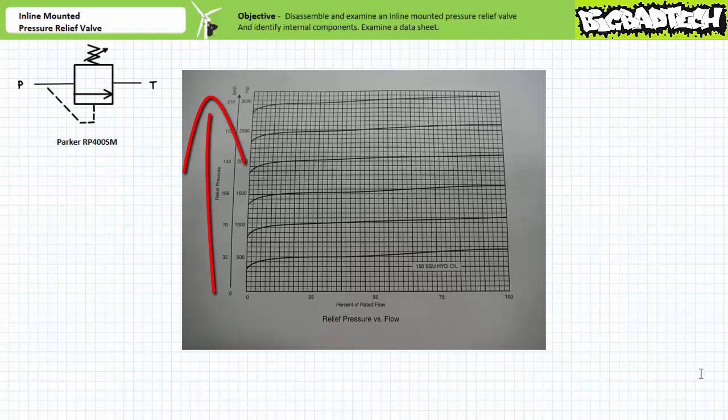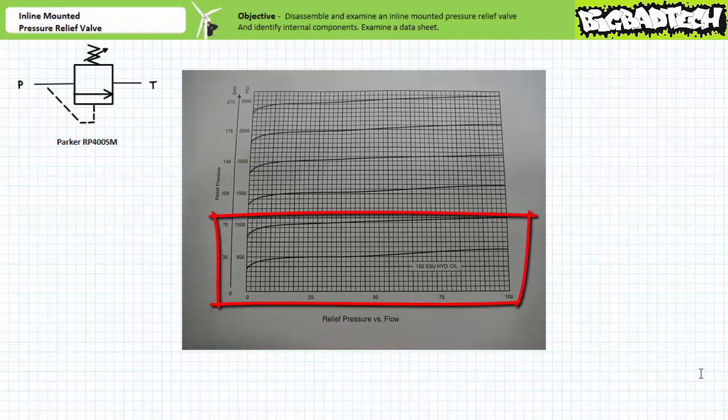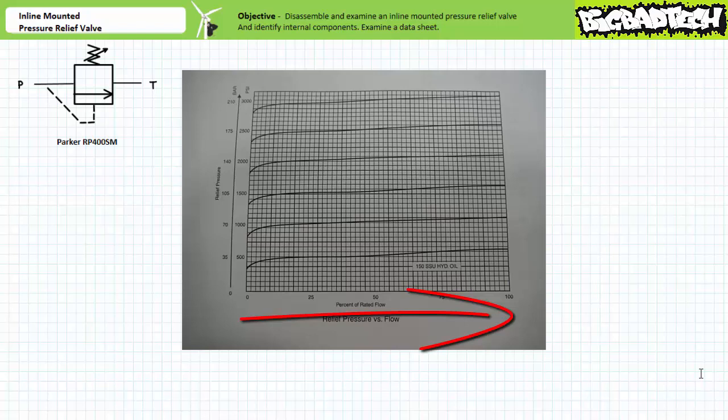The vertical scale is in units of bar and PSI. Given the pressure range of this valve is between 50 and 1000 PSI, we're obviously paying attention to the bottom region of this chart. The horizontal scale is percentage of rated flow. Given this particular valve is designed to accommodate a flow rate of up to 6 gallons per minute, 100% is 6 gallons per minute, 50% is 3 gallons per minute, and so on.